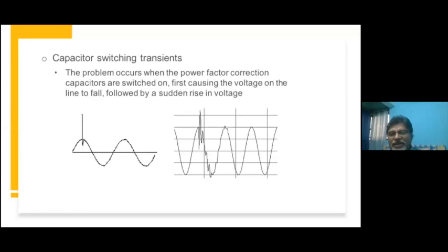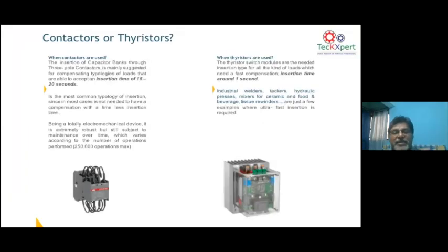So in this scenario, whether it's low voltage or high voltage, the surges are dependent on the loading of the network. You cannot connect a capacitor to a light load condition, because if you do, you will have these sort of oscillatory transients or voltages taking place. So that is what this slide is saying. Going to the next, you can control this in a low voltage system.